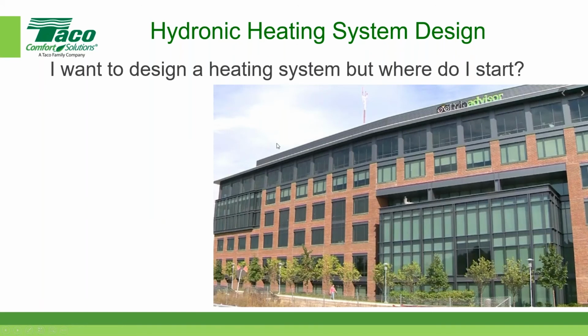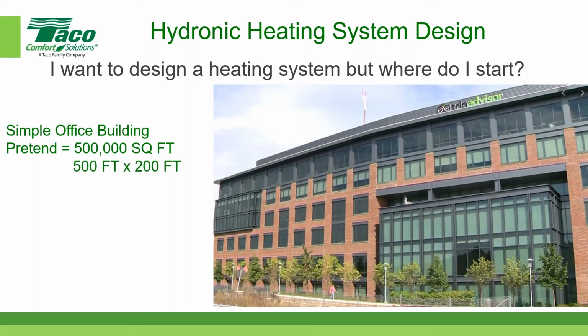So let's say I want to design a heating system, but where do I start? I always like to say I start with a building. In this case, we are going to have a simple office building. We are going to pretend that this building is 500,000 square feet, a simple rectangular building, 500 by 200. If you do the arithmetic, you'll find that is equal to 100,000 square feet. So the footprint of the building would be 100,000 square feet.